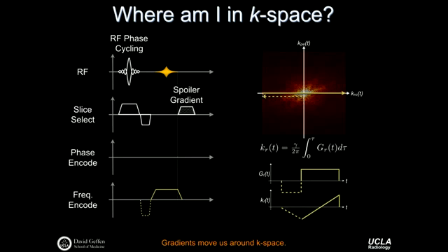Now, at every, say, point in k-space, and we have to talk about what we really mean by a point in k-space, we'll get to that later, at every point in k-space, remember, my spins are zipping past my coil thousands of times, and that gives me the flux I need to measure the amplitude of that spatial frequency. And because my gradient is just on and continuously on, I'm just continuously moving across k-space. And I'm actually doing that relatively slowly compared to the Larmor frequency. So at the Larmor frequency, I'm zipping past my coil 1,000 times, and then I sort of move to another point in k-space, and I effectively zip past it 1,000 more times, until I've visited all the different k points that I need to reconstruct the image that I have asked for.